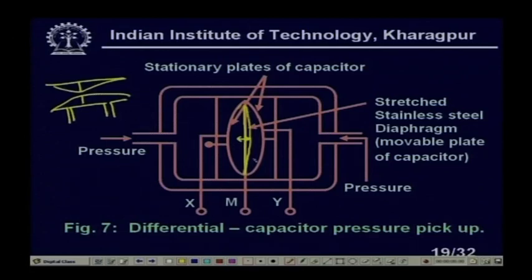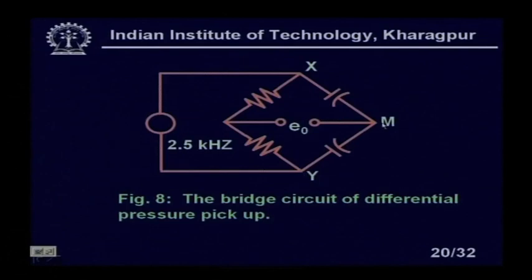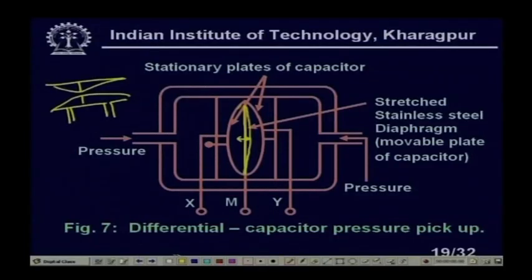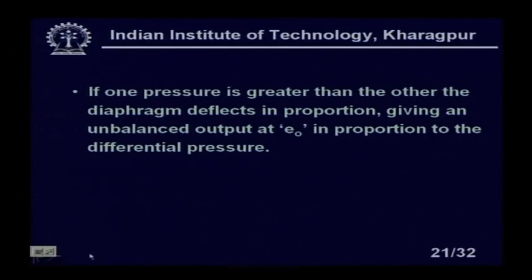The bridge circuit for the differential pressure pickup has X, Y, and M as the oval plates with two capacitors. If the diaphragm deflects in proportion to the pressure difference, it gives an unbalanced output E₀ proportional to the differential pressure. For the opposite pressure difference, E₀ shows a 180-degree phase difference. So it is difficult to determine the direction of deflection from the magnitude alone.